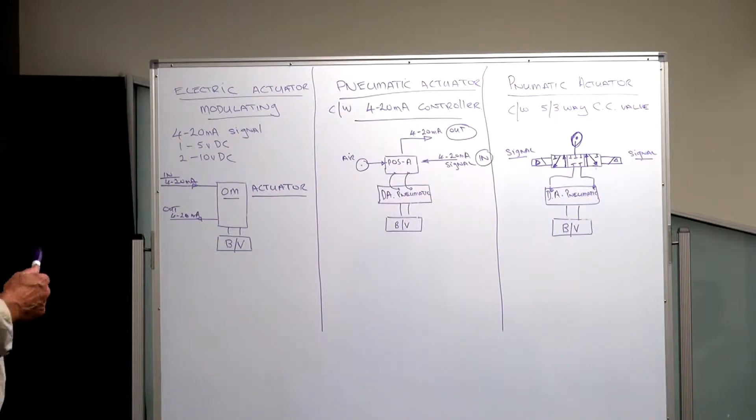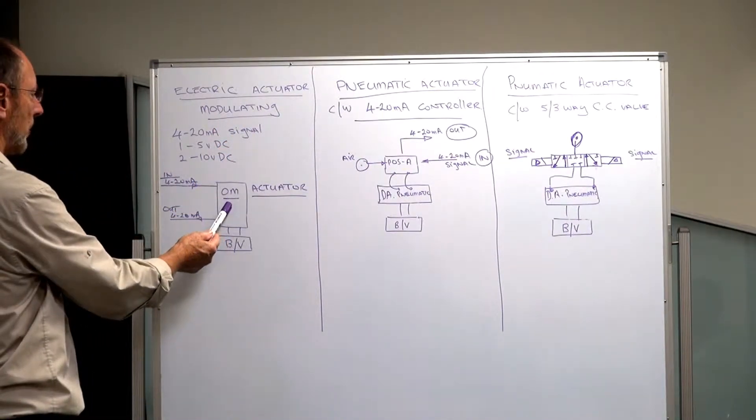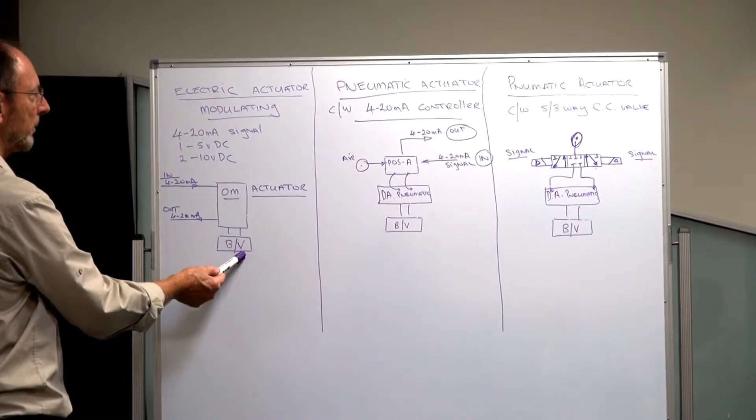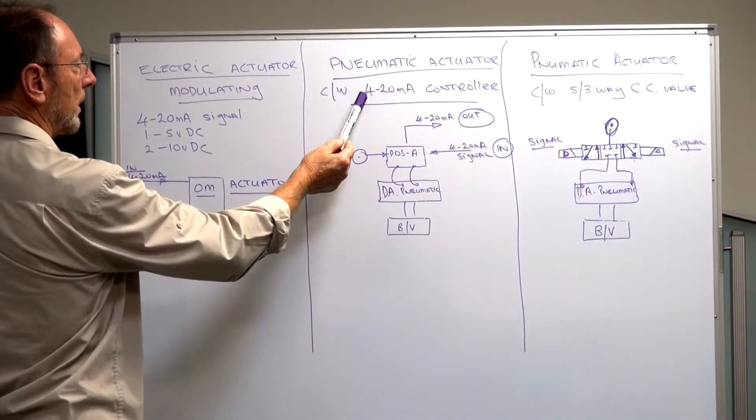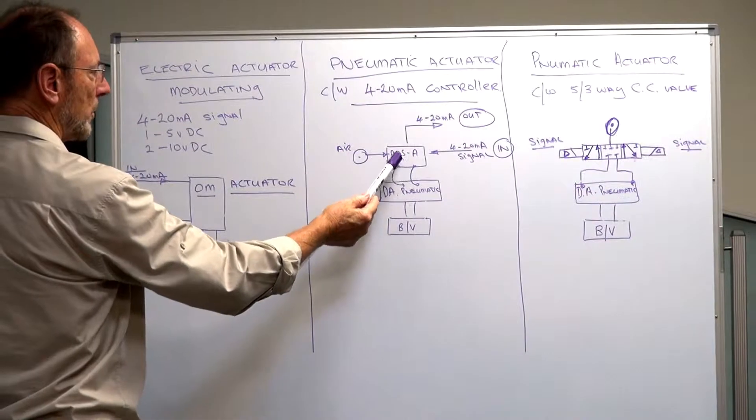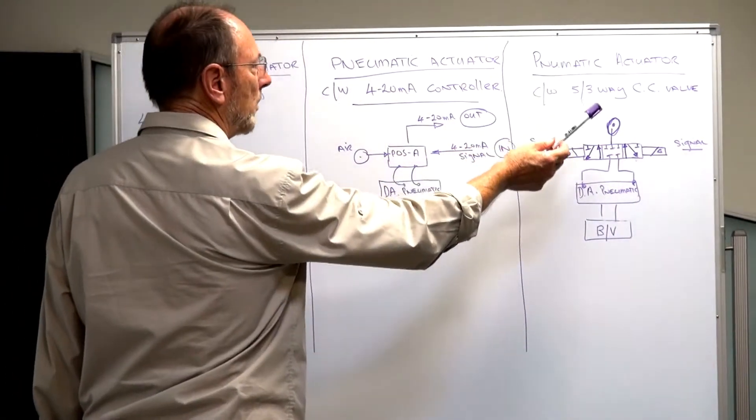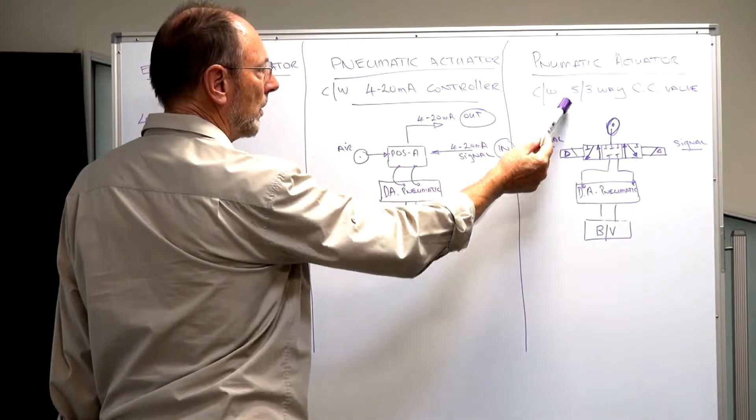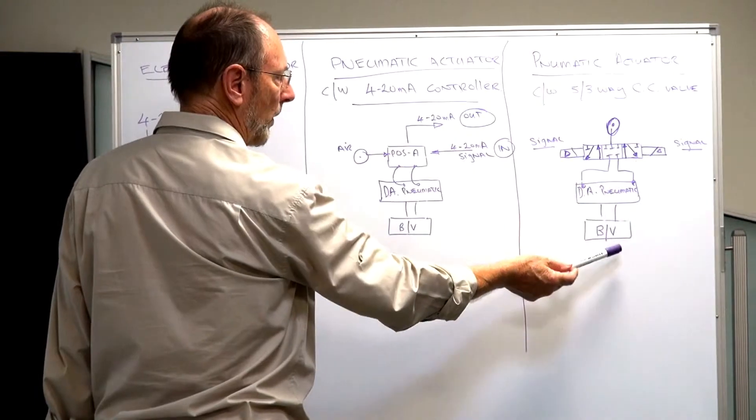We have three different applications for modulating actuation. Electric actuator modulating using a fully motorized valve control valve operating a ball valve or butterfly valve. Pneumatic actuator with a pneumatic electric controller which is controlling a double acting actuator and ball valve. And we have a pneumatic actuator complete with a solenoid valve with five three center control which we can inch the actuator opening and closing, so of a double acting actuator and ball valve or butterfly valve.